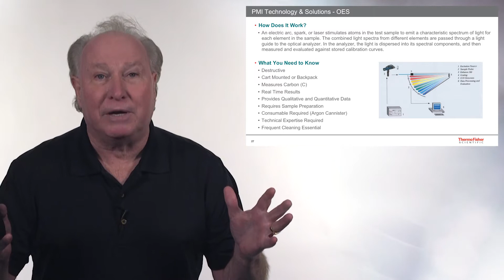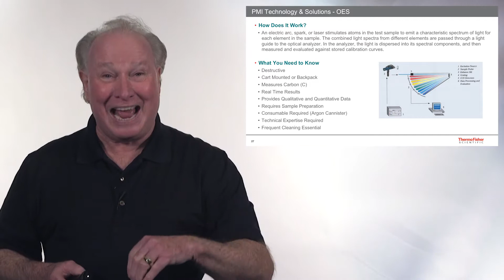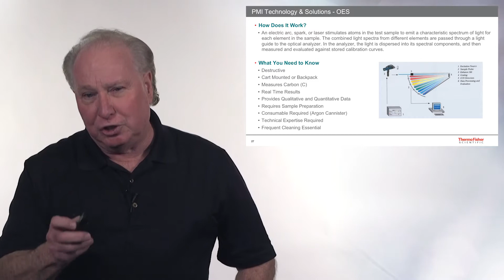This is optics. OES requires, and LIBS, that the instrument warm up and stabilize. XRF, on the other hand, cools down. That detector on XRF actually is minus 27 degrees centigrade. This warms up. So you really need some expertise and capability to use these devices to let them do the job that they want to do.